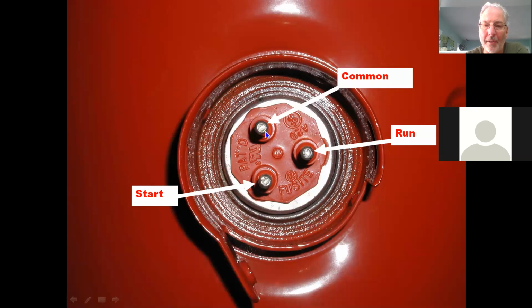And the lowest one is run to common. So you can pin down which one is your common, run and start if it's not marked or if you can't see it. There is a way to figure out which is which on there. And again, on some of these units, if you reverse the start and the run, you could have the compressor running backwards. Does someone have a question?